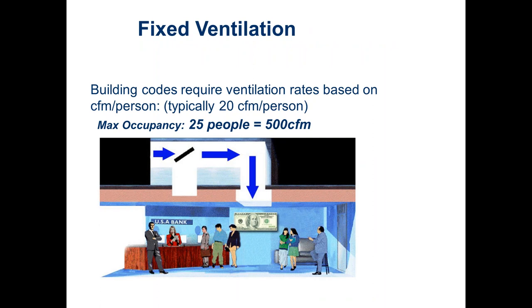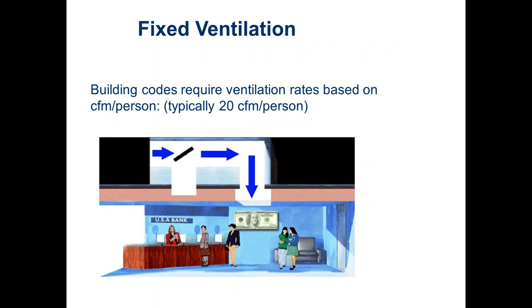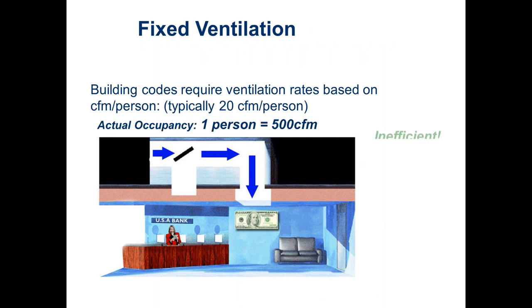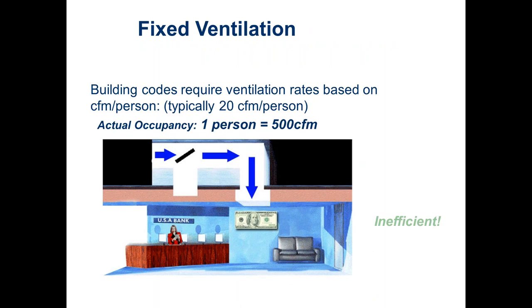In a typical building based on 20 CFM per person, if we had 25 people designed to be in a space, we'd have to bring in 500 CFM of outside air. But later in the day with only five people, we'd still bring in 500 CFM. At night with just one person, we'd still be bringing in 500 CFM. The building and system have no idea how many people are in there, hence it doesn't know how much outside air to bring in — it always brings in the code-required design amount. That's what we need to change.